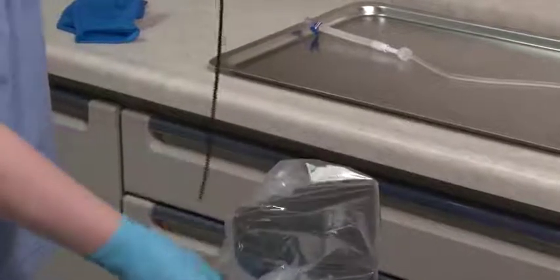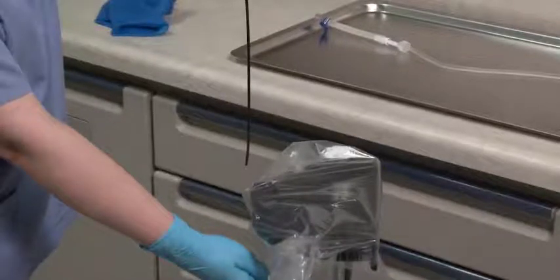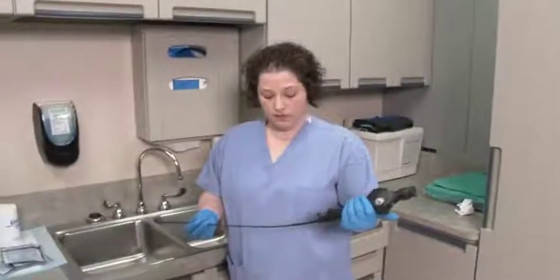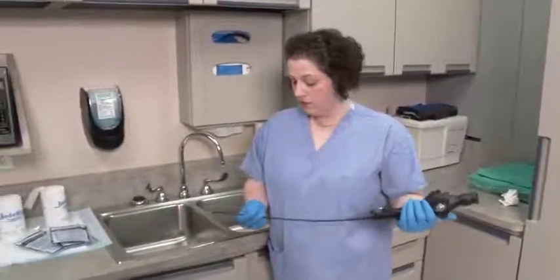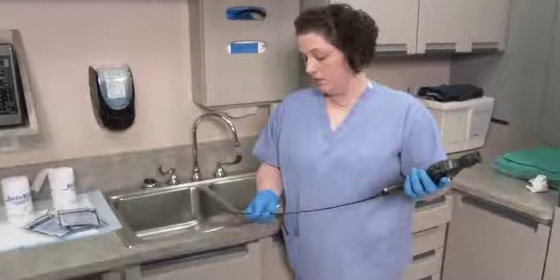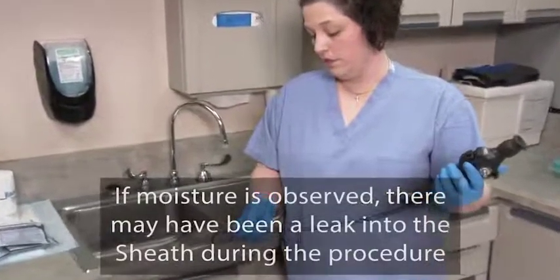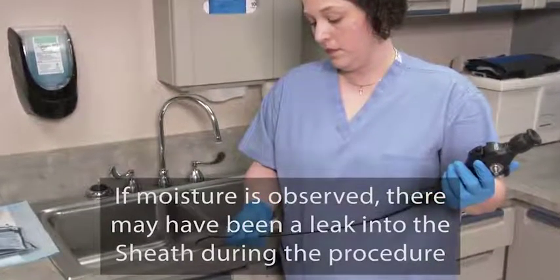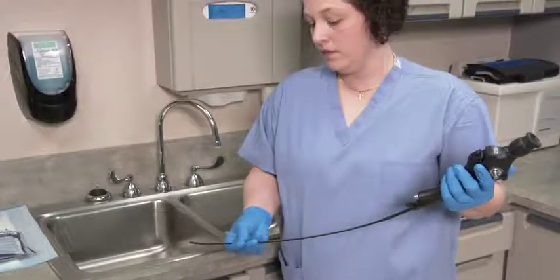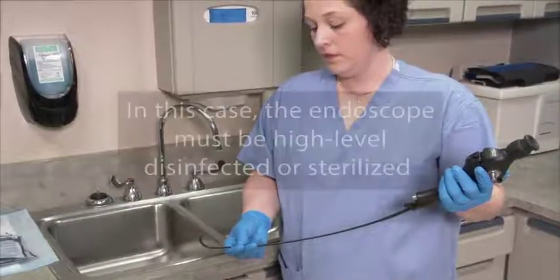Do not twist the endoscope when removing it from the sheath. Doing so can damage the insertion tube. If you experience difficulty removing the endoscope from the sheath, do not use excessive force in trying to remove it. Inspect the insertion tube and distal tip and confirm that these areas are dry. If moisture is observed, there may have been a leak into the sheath during the procedure, provided that the endoscope was dry when the sheath was attached. In this case, the endoscope must be high-level disinfected or sterilized.